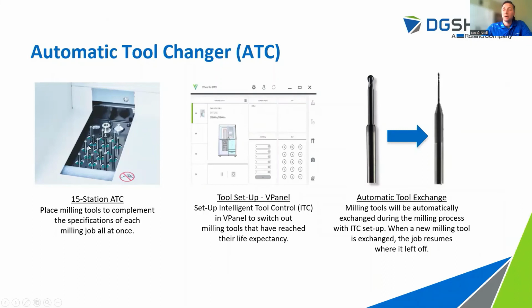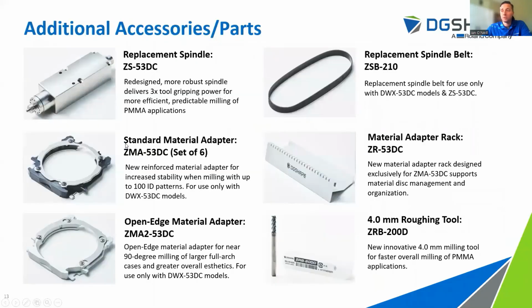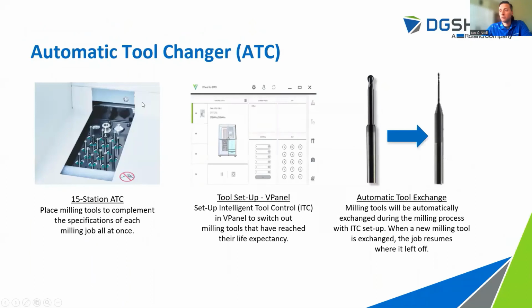As I mentioned before, that tool holder is now moved into its own compartment. We can see an image of that here. I will point out something I should make you aware of if you are a DGSHAPE user already. With this machine, the calibration tool is no longer kept inside of the tool changer. That tool, the calibration pin, should be kept in the drawer with the calibration device. When you need to perform a calibration, that calibration pin would be put in slot 15. Whatever tool you have in slot 15 when performing a calibration would have to be removed, and you would replace it with the calibration pin, place your calibration jig into the changer, and start your calibration.